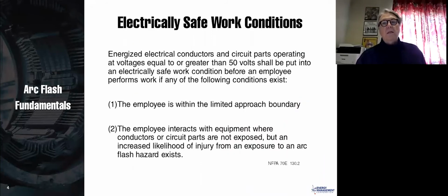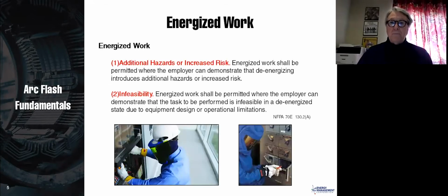Now, this basically says that if you are within the limited approach boundary, which for most low voltage systems is 3.5 feet, and it's over 50 volts, that you are required to lock out the gear. There are two exceptions to being able to lock out the gear. One is if you have additional hazards or increased risk. For instance, if de-energizing would cause more danger than working hot, then you are allowed to work hot.